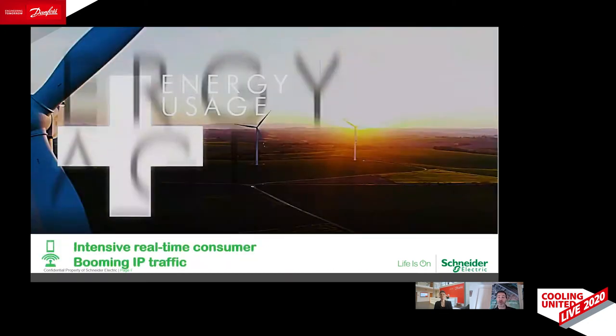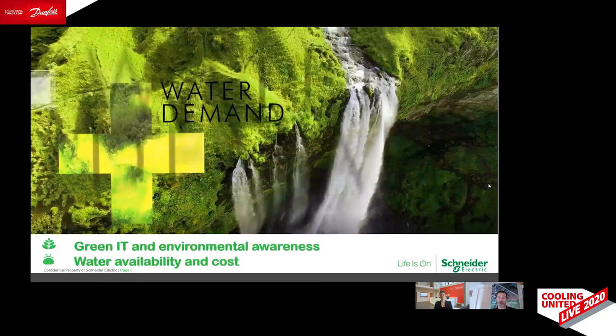Together with the energy usage, data centers are one of the most impacting human activities globally, both on water consumption and energy consumption. Cooling is absorbing more or less 40% of the power consumption in data centers. So every action we do on cooling has a direct impact on the data center efficiency and the global usage of energy. Certainly using water with evaporative systems is a good choice, but even water is a big issue or will be a big issue.